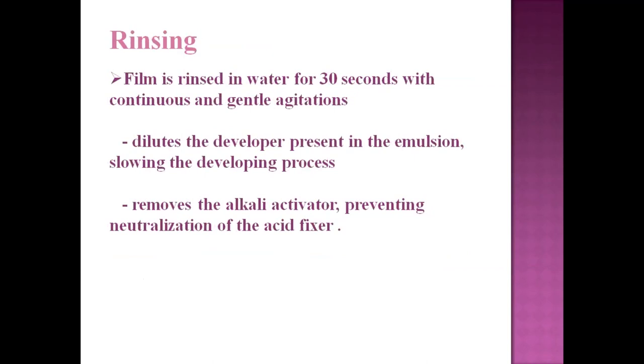After developing, we go to the rinsing process. The film is rinsed in water for 30 seconds with continuous agitation to remove all developing solution. This dilutes the developer in the emulsion, slows the developing process, and removes the alkali activator, preventing neutralization of the acid fixer, since the developer is alkaline and the fixer is acidic.